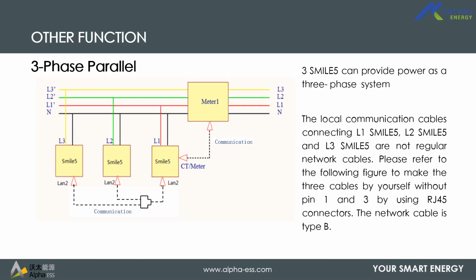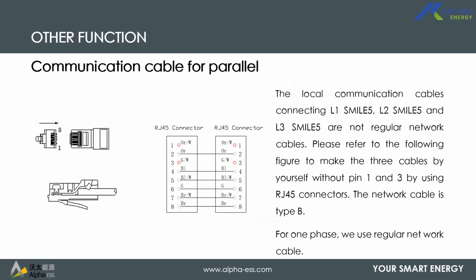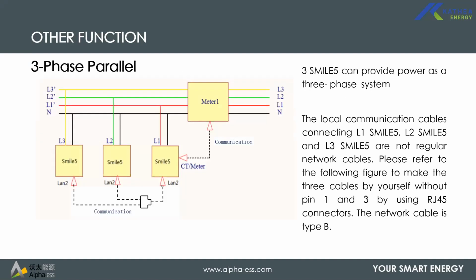However, you would need an RJ45 coupler, which would couple your master inverter to the other two inverters. So basically, you need the switch, and the cable used is a type B. So this is the cable orientation, how you should crimp it. All this information is supplied with the manual. With a three-phase situation, you'd have your system with three inverters, one on each phase, and the system can produce three-phase power at a standard phase angle, and each inverter can overload separately. If one inverter overloads, the whole system shuts down since it's operating as a three-phase system.